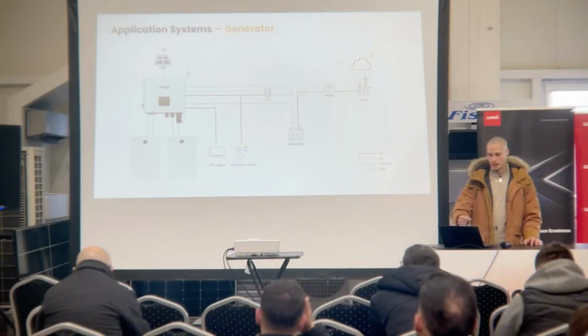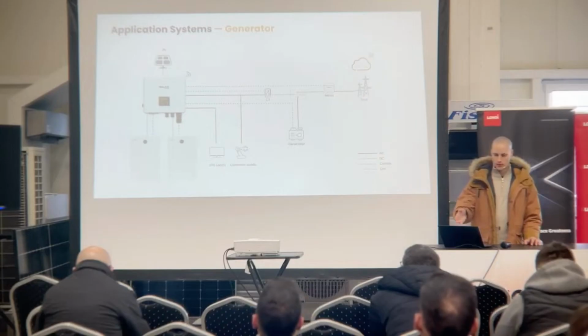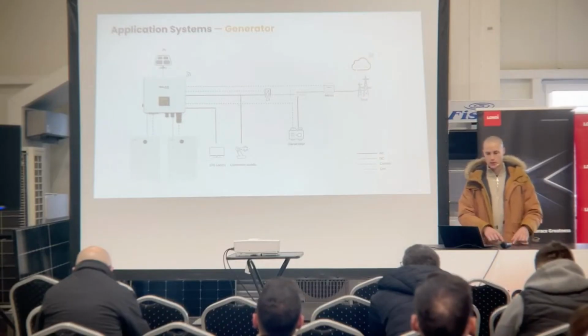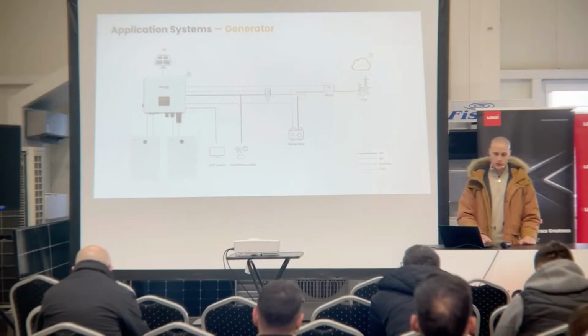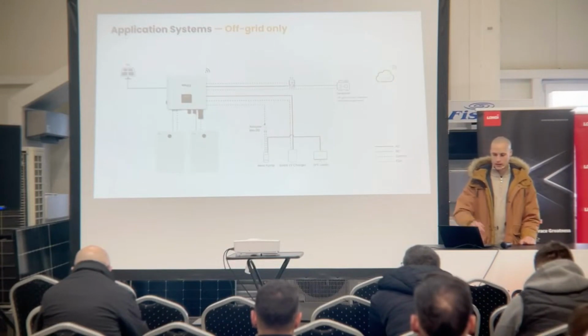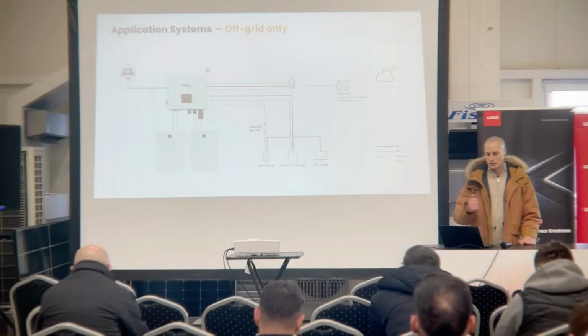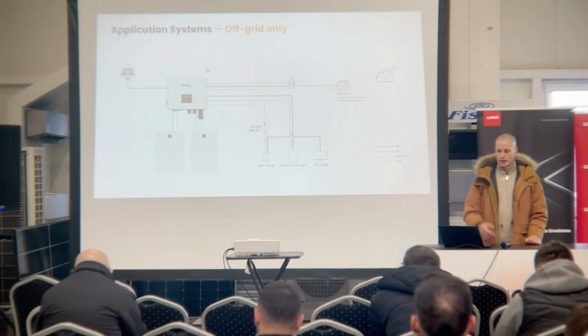In this case, it's on-grid, but as you can see, we can still use the EPS loads, the common loads, and we can use the generator's power in case the grid goes into outage. So you just need to install an external ATS that will do the switching between the grid and the generator. But in case we're just talking about off-grid solutions, then it's going to be this one, where you have to connect the generator on the grid side, just use a CT, and on the EPS side you have all the loads.